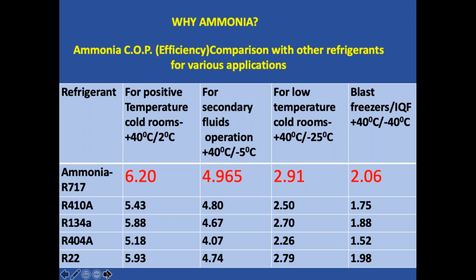In chilled water plants, we use 12 degrees, 7 degrees, so 2 degrees evaporating temperature. Secondary fluids for process plants like brine, if you use ethylene glycol or propylene glycol, minus 5 degrees centigrade. For food preservation, that is ice cream, meat, fish, minus 20 degrees centigrade, so I have taken minus 25 as the evaporating temperature. And lastly, the freezing application, which is minus 40 degrees. All freezing applications are done at minus 40 degrees centigrade.